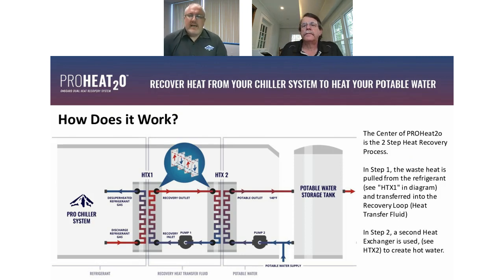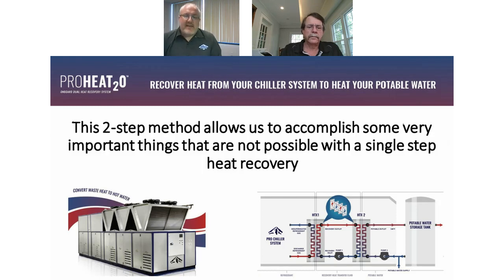So how does it work? At the center of the ProHeat2O is the two-step heat recovery process. In step one, the waste heat is pulled from the refrigerant. If you notice heat exchanger 1 in the diagram, we transfer that heat into the recovery loop. That's our heat transfer fluid that's moving through there. Then we go into step 2, where we're using a second heat exchanger, heat exchanger number 2, and that's where we're creating the hot water. That two-step method allows us to accomplish some very important things that aren't quite possible with a single-step heat recovery.